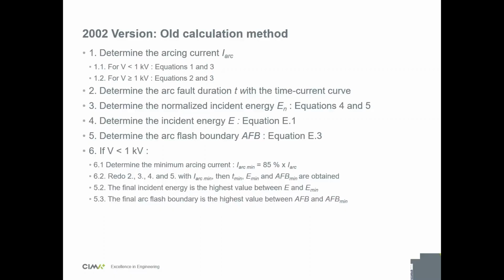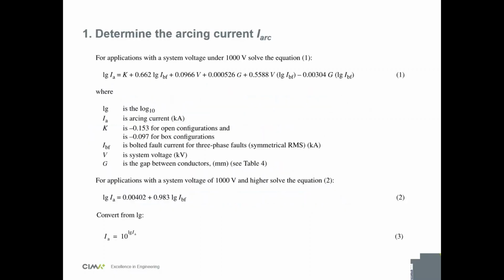And then if you're below 1 kV, you need to do a second arcing current, which is equal to 85% of the arcing current. And then you calculate the energy with that one. In some cases it's larger, sometimes it's smaller than the original arcing current. And then you choose the largest value between the two. So the equations, for example, you have as an input the K factor, which says open configuration or inside a box. You had your fault current, you had the voltage, you had the distance between the phases, so the gap. You plug that in a logarithmic equation, then you say 10 to the log IA, and you get your arcing current.